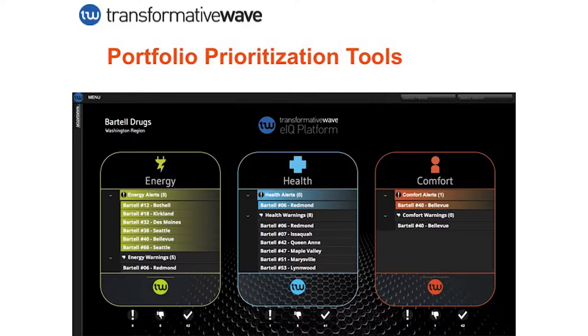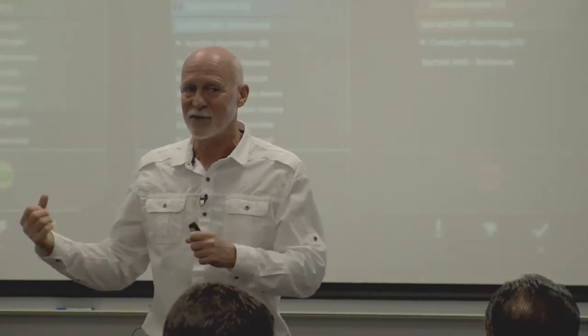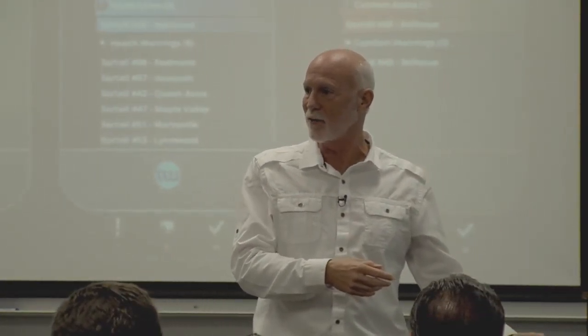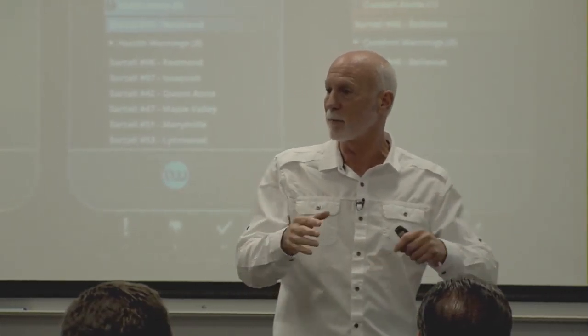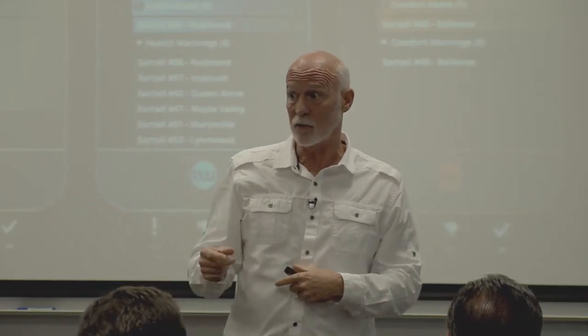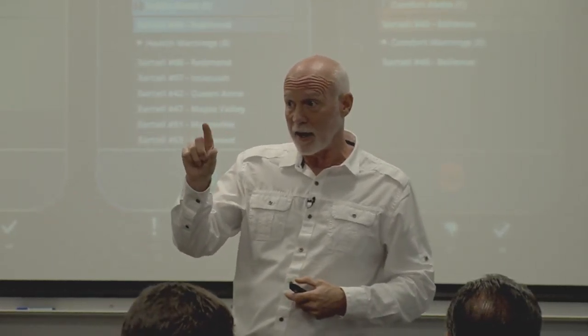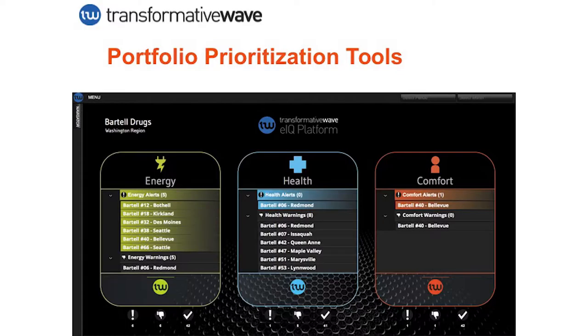You're describing a situation that's actually fairly common. We run into this as an HVAC service provider where we're there to fix the equipment, but we're not the controls guys—they have Trane or somebody else, could be a supermarket chain with Emerson CPC, whatever it is. So the HVAC guys have to call the controls guys to make an adjustment or to test, because there's authority there, and it's tough to have any good local authority. With a Trane tracer system, you may or may not have a dial you can actually affect—a lot of times they're just a blank sensor, so you're limited. Maybe you have a push button, right?